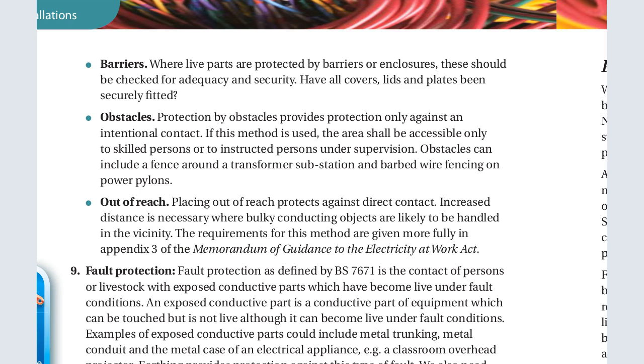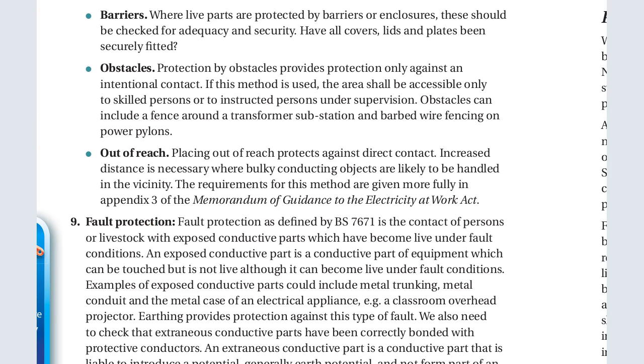That is, protection by obstacles provides protection only against intentional contact. If this method is used, the area shall be accessible only to skilled persons or to instructed persons under supervision. Obstacles can include a fence around a transformer, substation, and barbed wire fencing on power pylons. So out of reach, there is another one called out of reach. The placing out of reach protects against direct contact, that is increased distance, is necessary where bulky conducting objects are likely to be handled in the vicinity.